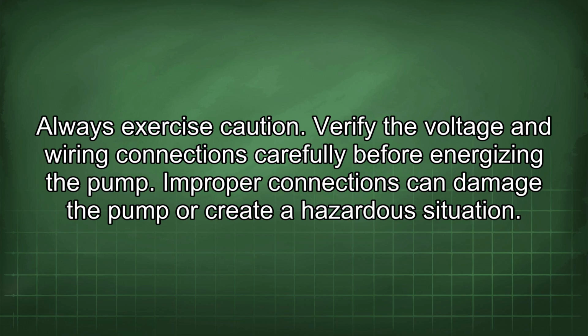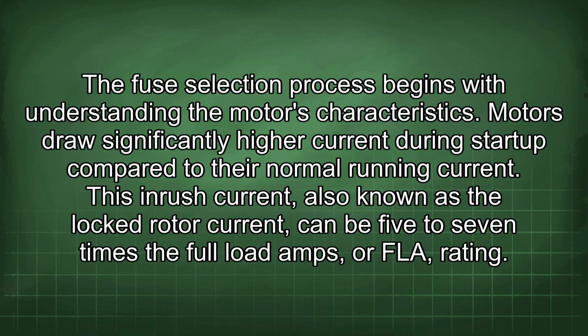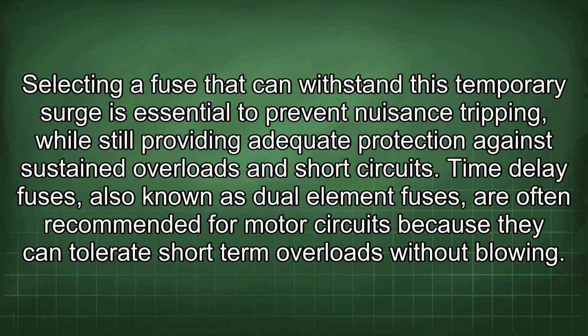Always exercise caution. Verify the voltage and wiring connections carefully before energizing the pump. Improper connections can damage the pump or create a hazardous situation. The fuse selection process begins with understanding the motor's characteristics. Motors draw significantly higher current during startup compared to their normal running current. This inrush current, also known as the locked rotor current, can be 5 to 7 times the full load amps, or FLA, rating. Selecting a fuse that can withstand this temporary surge is essential to prevent nuisance tripping, while still providing adequate protection against sustained overloads and short circuits.